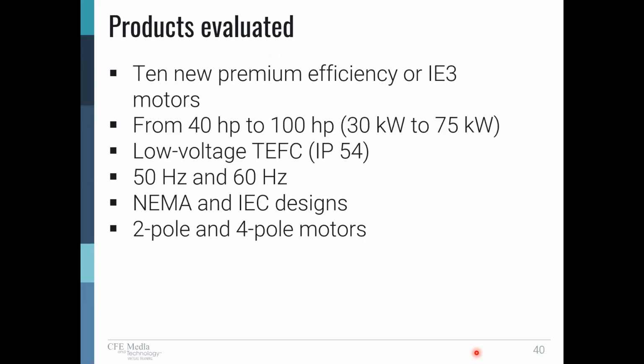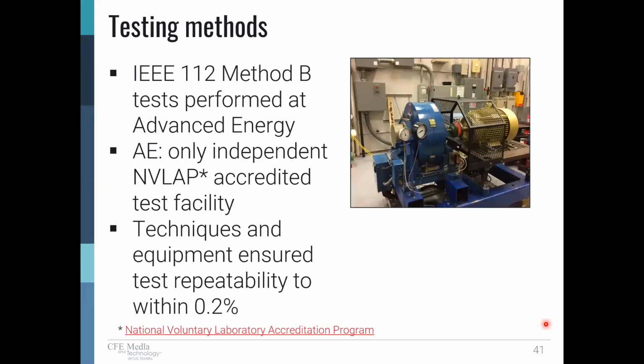Because we were linked up with our friends across the pond in the UK, we had 50 hertz motors as well as 60 hertz motors. NEMA machines and IEC machines, 2-pole and 4-pole motors. The test method that was used is called IEEE 112 Method B, which is a dynamometer test. And that is harmonized with the IEC test standard for efficiency, IEC 60034-2-1. And Advanced Energy is the only independent NVLAP accredited test facility.